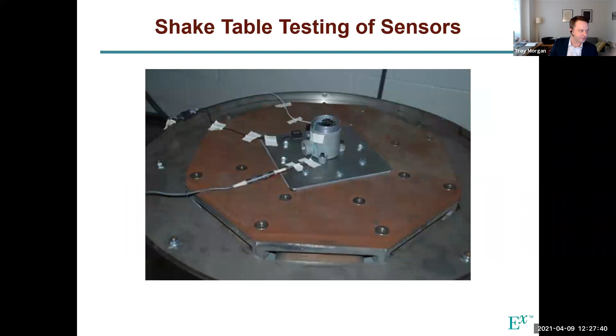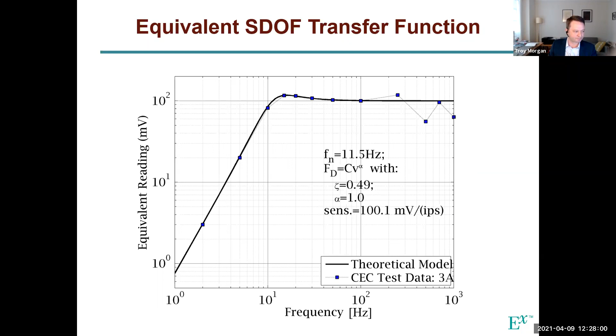We confirmed that for low levels of velocity input, the frequency response function was essentially represented by a linear, classic system. But when we looked at different amplitudes of input, we found that as the velocity amplitude got higher, say from 1 inch per second up to 6, we saw evidence of impact of the coil with the casing.